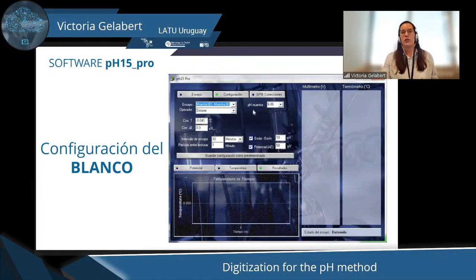And that's by doing what I'm about to do right now. The software is going to allow me to carry out this configuration. And then what I'm going to try to enter here is the correction of the thermometer, because I'm having a look at the temperature live at the moment. And I'm also going to correct the multimeter. And at the same time, this sector down here was what I was looking at before, the electrochemical balance. During 30 minutes, we're going to have a look at the potential difference between both compartments. And we want to make sure that this isn't higher than 10 microvolts.